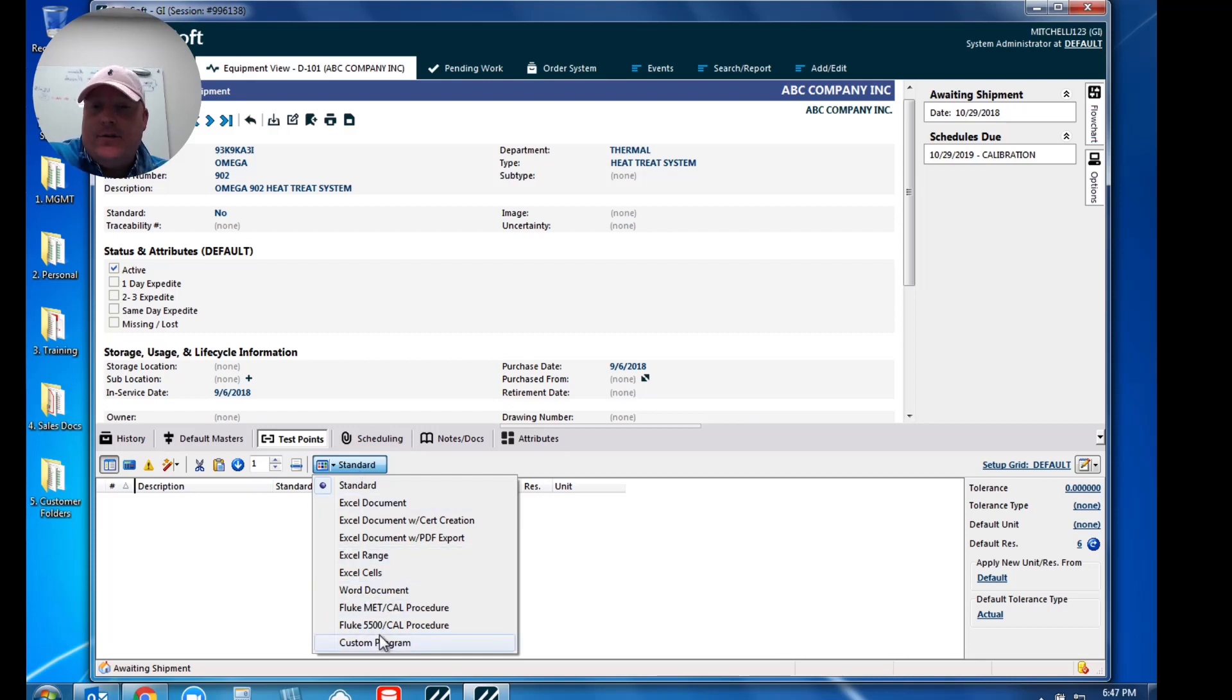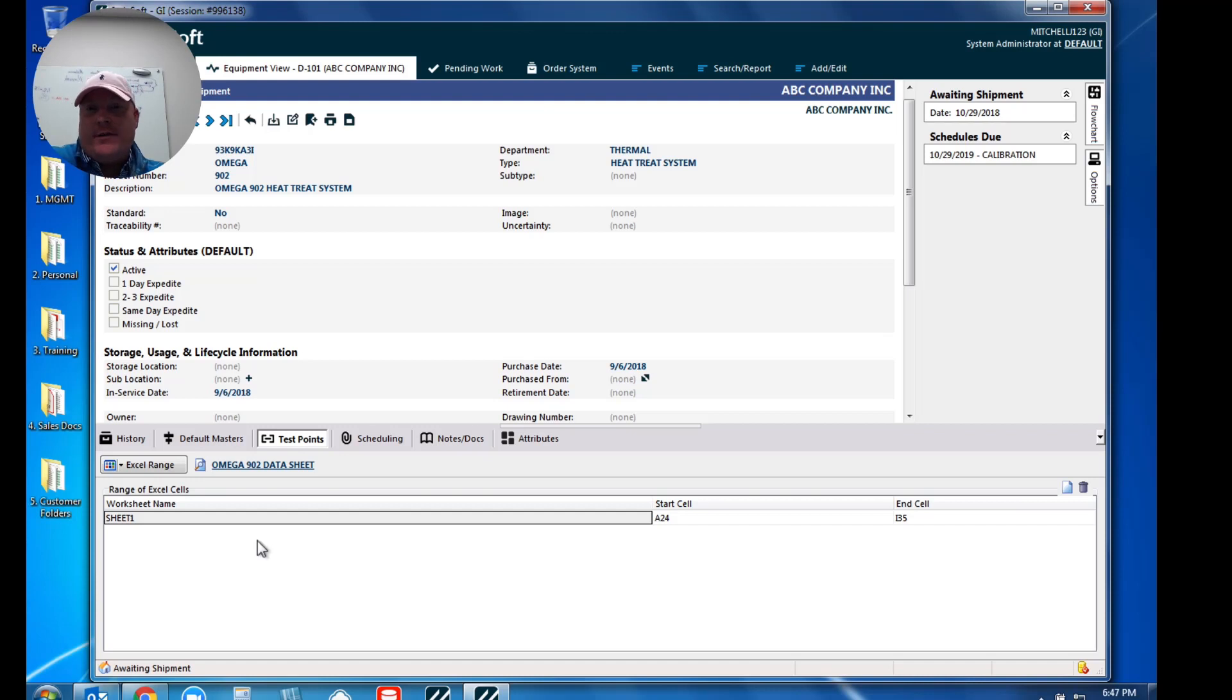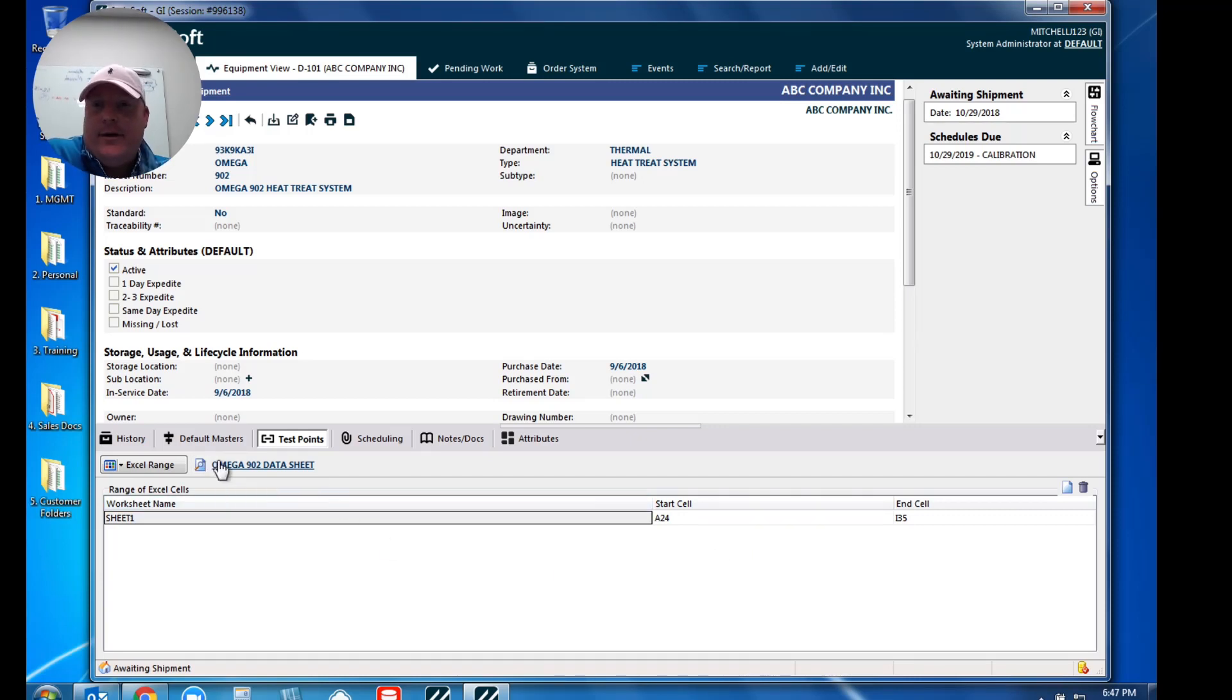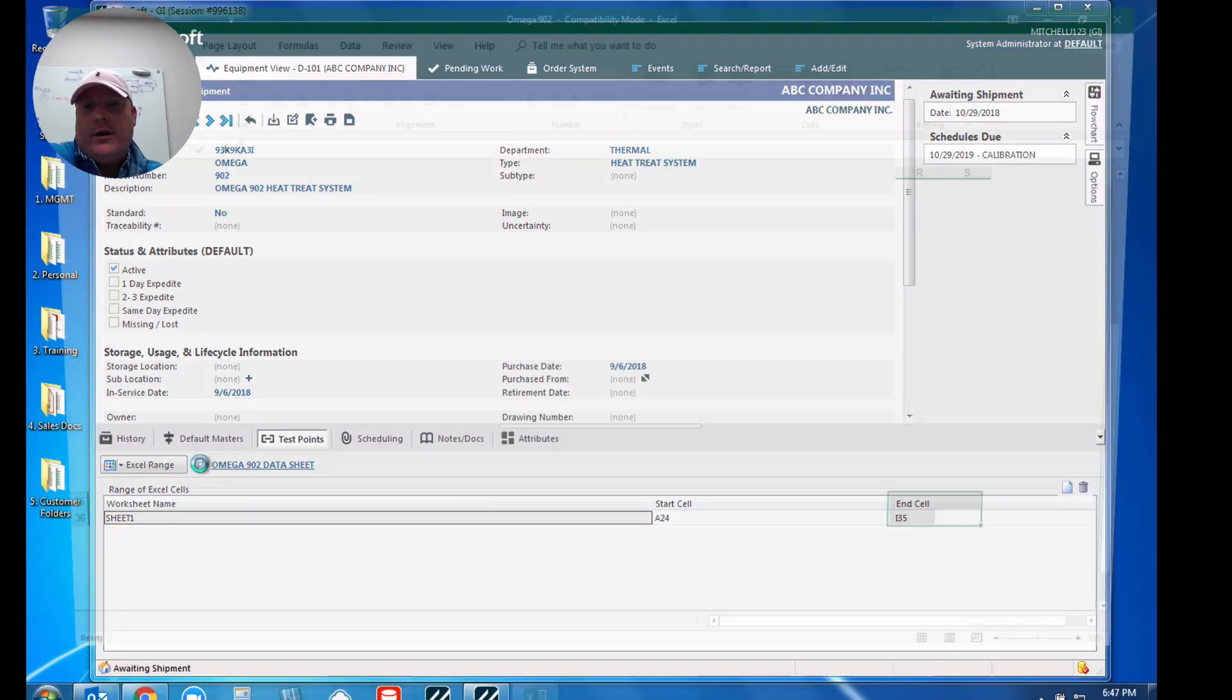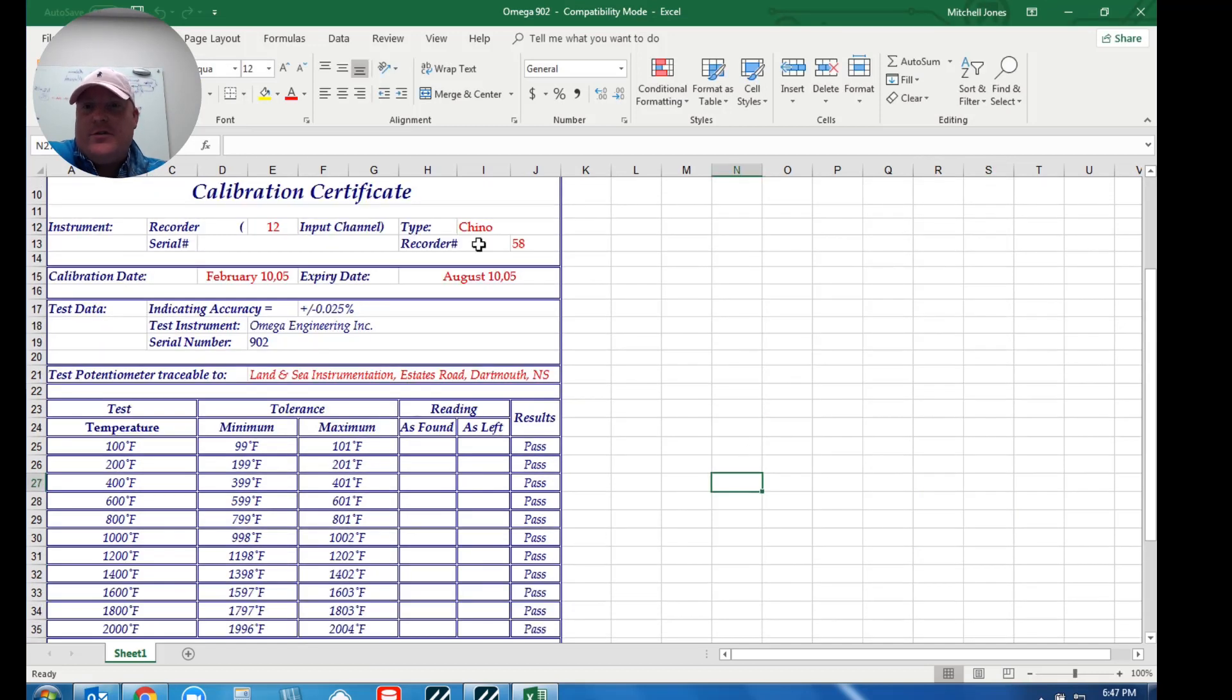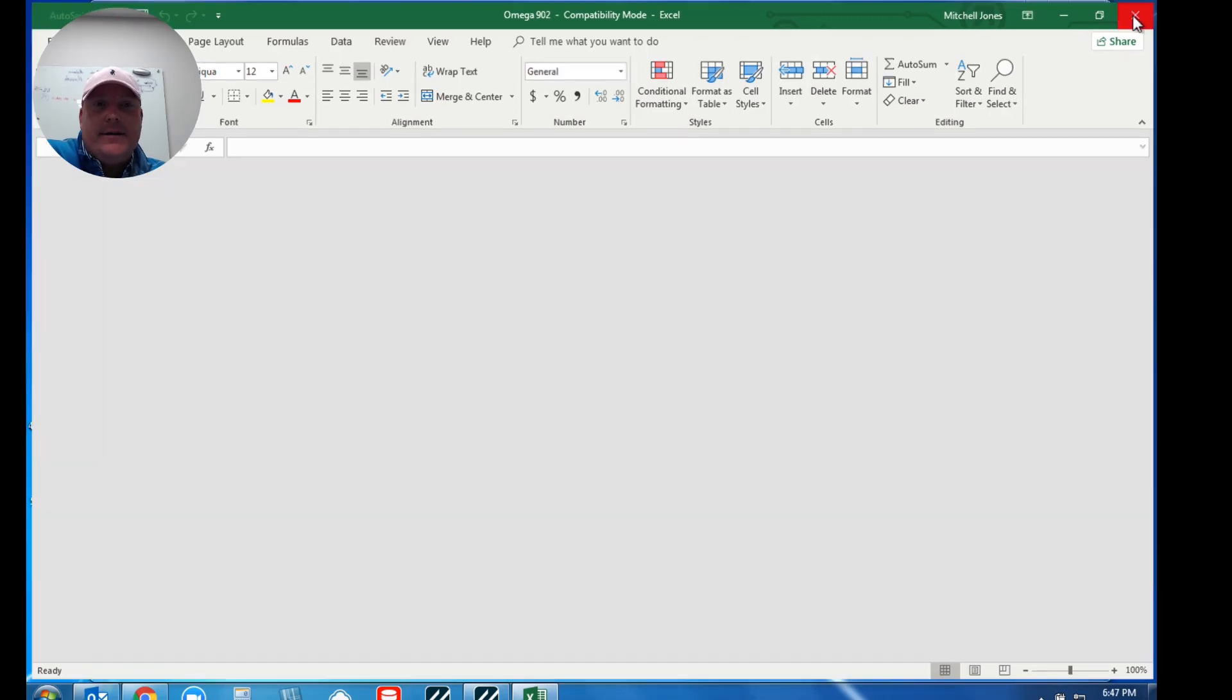But in this video I want to point out Excel range, and what this allows us to do is I've got this Excel file. So when I go to perform my calibration event, it's going to open up that Excel file and then I get to actually specify which portions of that Excel file are going to get embedded within my certificate. So you'll notice here I've got some stuff preset up. I've got my Omega 902 data sheet pre-configured. When I go to view that, we do give you a quick viewing option where I can actually take a look at that Excel file.